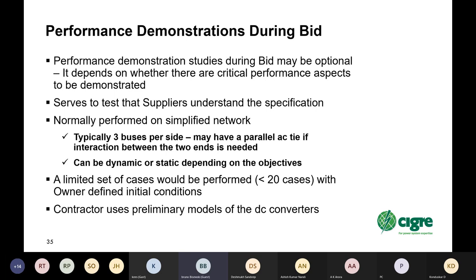Normally, it's performed on a simplified network. Typically, you might have three buses per side. If you have a performance requirement where the DC is embedded in an AC system, you may need to model the parallel AC tie so that the interaction between the two ends can be modeled and evaluated. The equivalence can be dynamic or static, depending on the objectives. And usually you would include a limited number of cases, probably less than 20 cases, where you define the initial conditions and require the cases to be performed. Then you can do an evaluation of the capability and the performance of the supplier's equipment at the bid stage. In this case, the contractor uses preliminary models of his DC converters, obviously not optimized yet, but at least it shows you that the DC will work in your case and meet your performance needs.